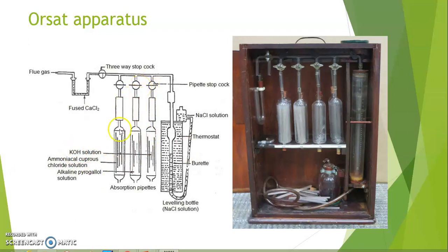In the second absorption chamber, an alkaline pyrogallol solution is used — it is an ammoniacal pyrogallol solution. This basic reagent is used to absorb the incoming oxygen gas from the flue gas sample.